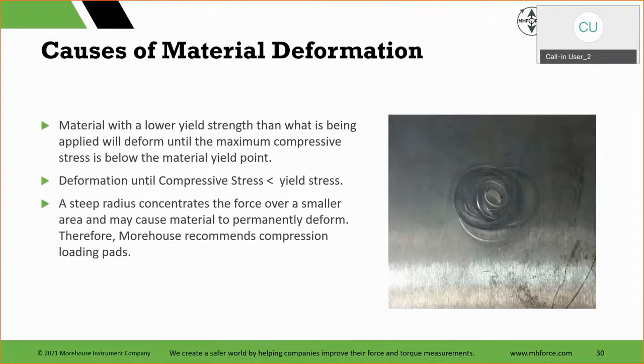Causes of material deformation. And here we have sacrificial blocks. You can see this block has been degraded. It's something else that we see in using the adapters. Adapters that are used for calibration should be sent with the load cell. And if this is the adapter that's used with it and it deforms, the recommendation is grinding, but at least you have that same hardness. And what really happens here is material with a lower yield strength than what is being applied will deform until the maximum compressive stress is below the material yield point. Deformation until compressive stress is less than yield stress. And then a steep radius concentrates the force over a smaller area and may cause material to permanently deform. And that's why we recommend compression loading pads. It's also what's happening with a load cell, right? If you're in compression, if you're in tension, you can just pull out the whole web element.